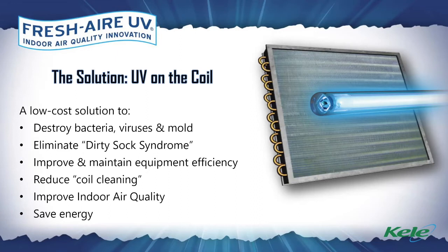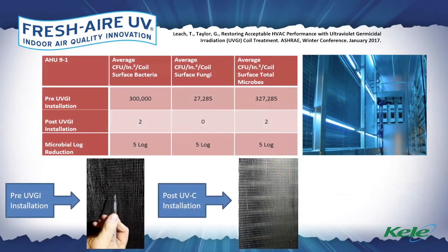And I often get asked, well, do we clean the coil first and then mount the UV system? Well, best practices would be yes, you clean the coil, or if it's a new coil, you mount it with the UV system already and you're in a much better position. But quite frankly, the most common is retrofit, and retrofit still makes up probably 90% of the UV market, and that's just mounting the UV system. And this here is a great example of just that.